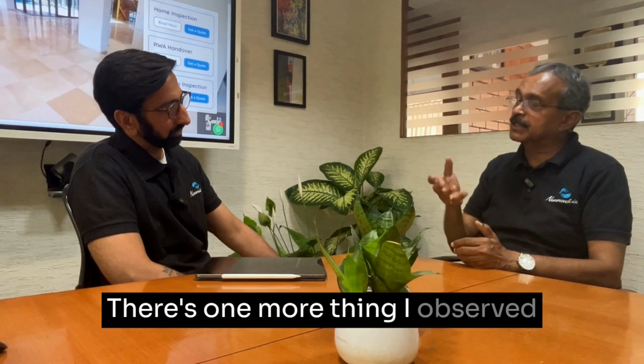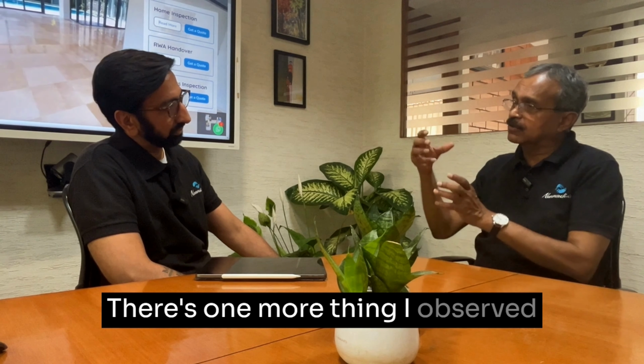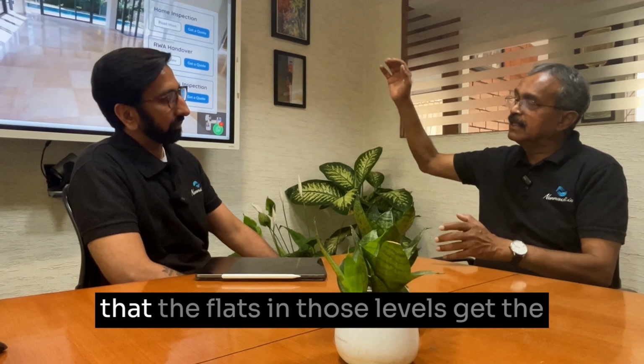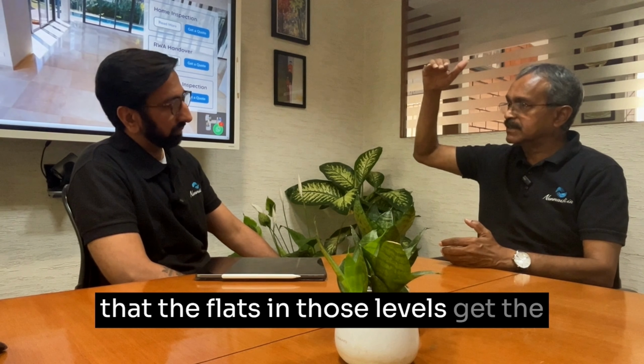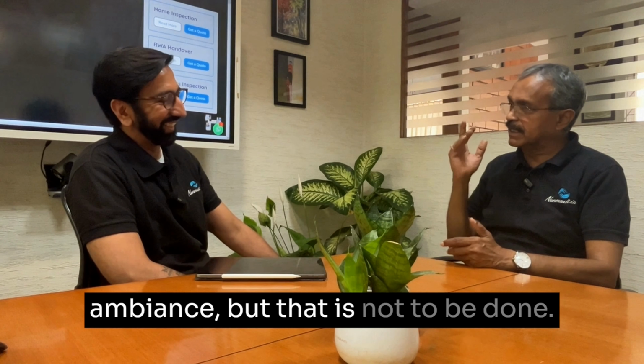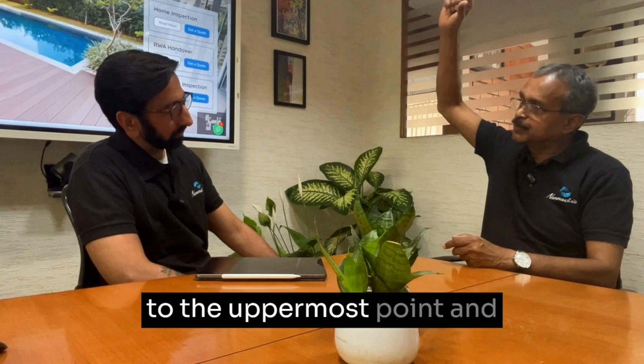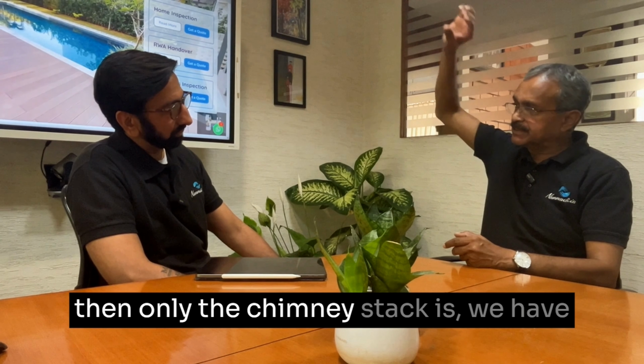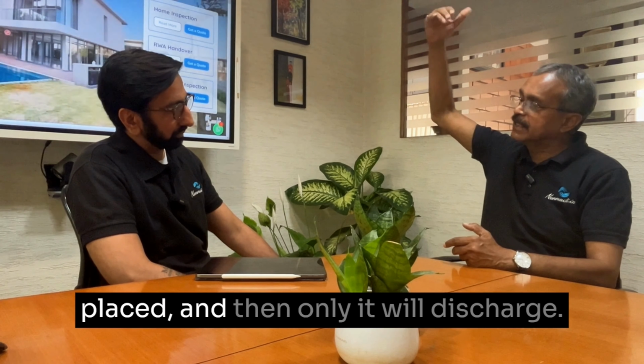There's one more thing I observed in many places: they discharge the outlet at some intermediate level, so the flats at those levels get the obnoxious smell. But that is not to be done. This discharge has to be taken to the uppermost point, and only then should the chimney stack be placed to discharge it.